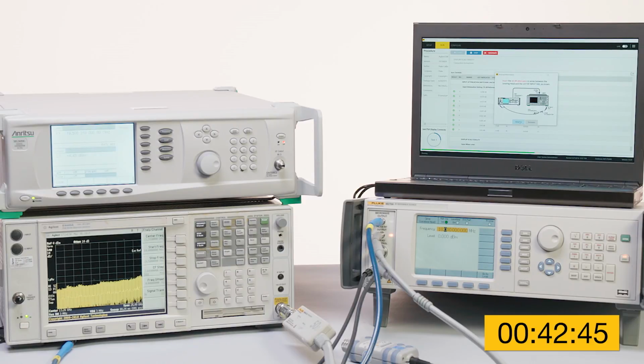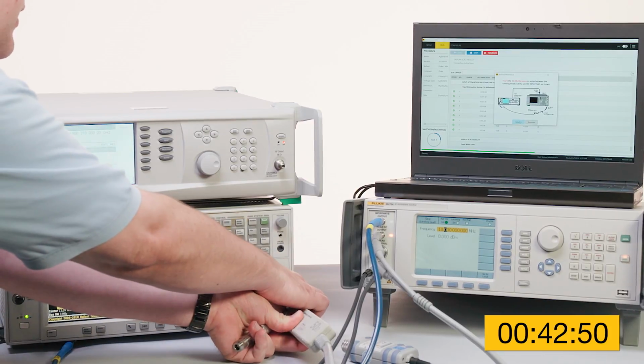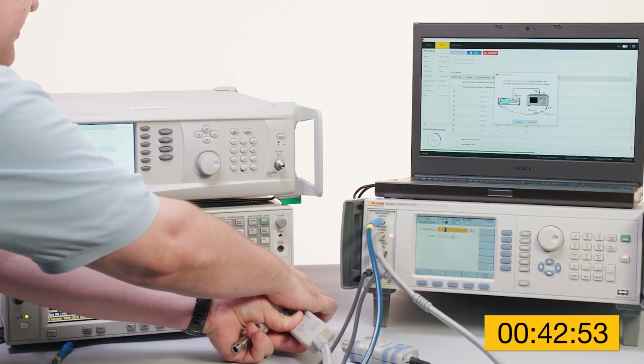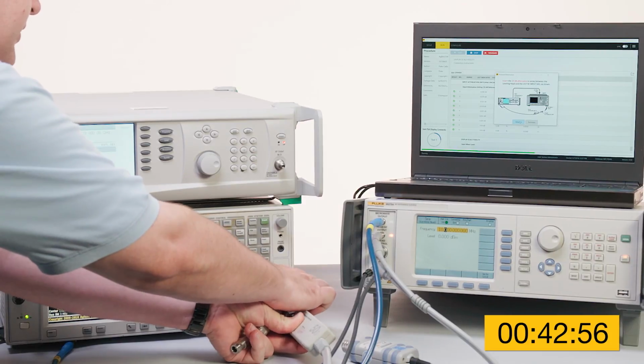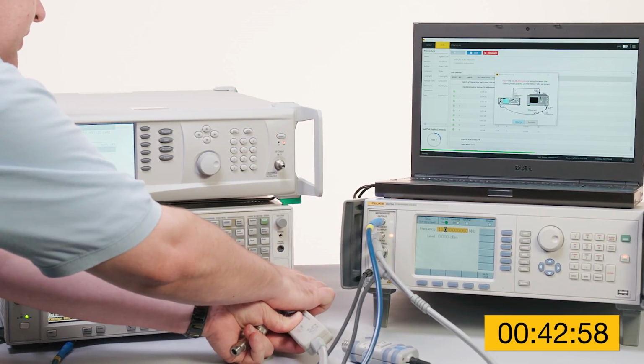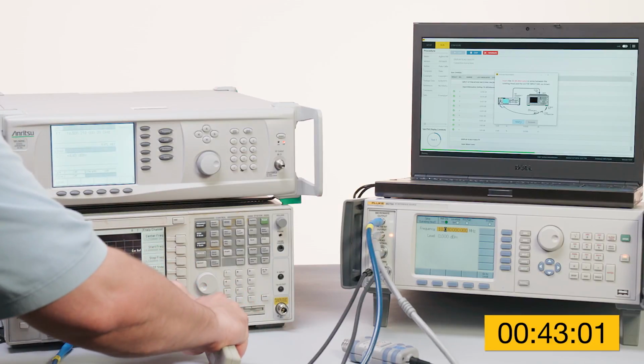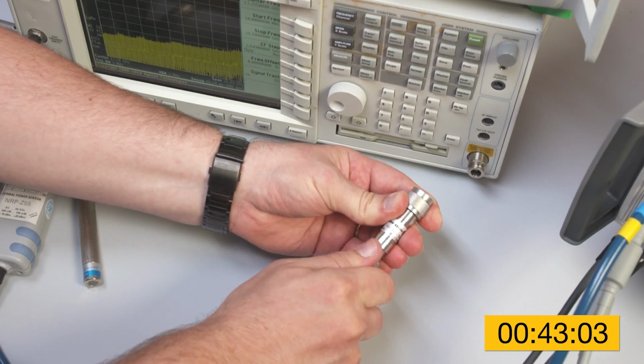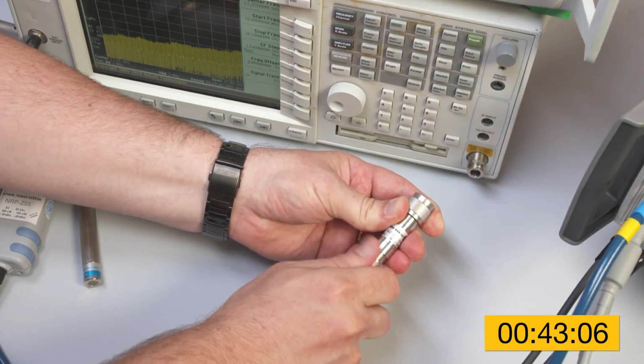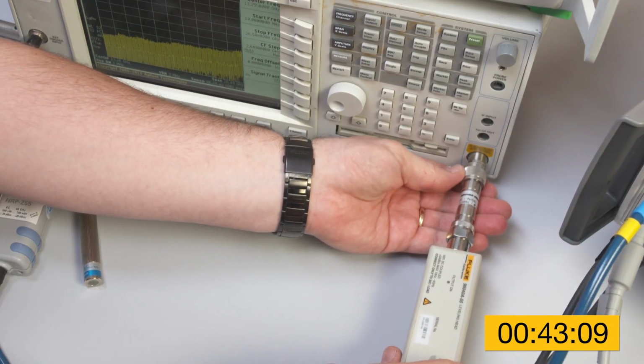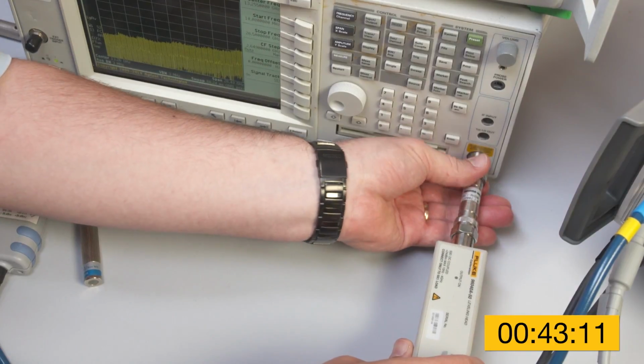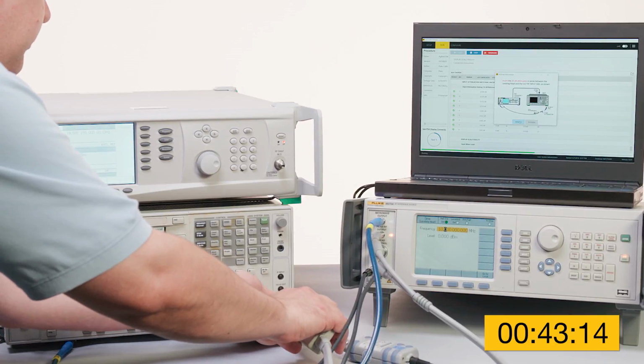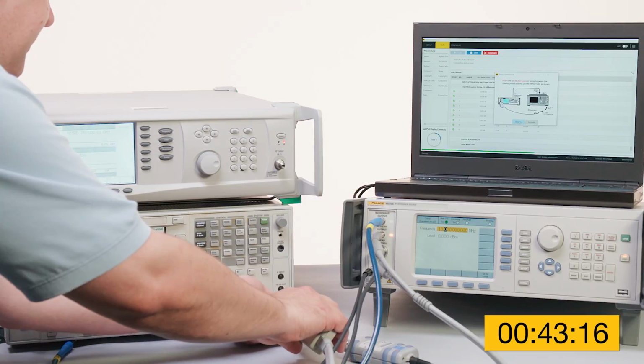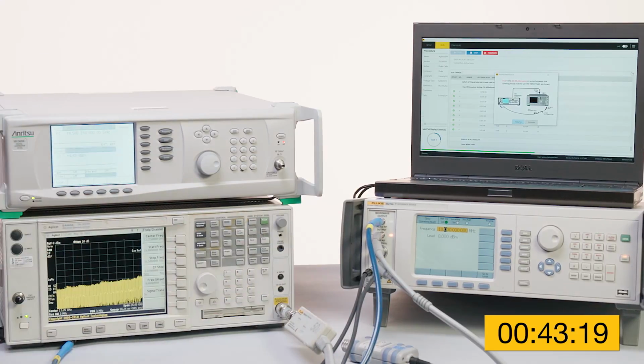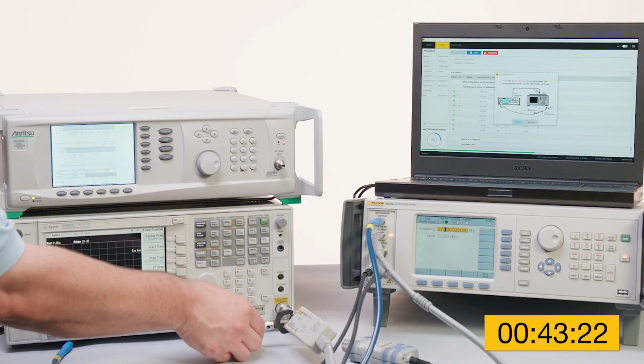Okay, we are now to the next connection message, which is part of the display scale fidelity test. Metcal is asking me to remove the 10 dB attenuator and insert the 20 dB attenuator in its place. Again, we are just trying to keep the output level of the 96270 in its prime operating range, also known as the sweet spot. And by inserting this attenuator and re-establishing our previously recorded reference, we are able to continue with this test while keeping the output level of the 96270 high enough that we stay in that prime operating range.